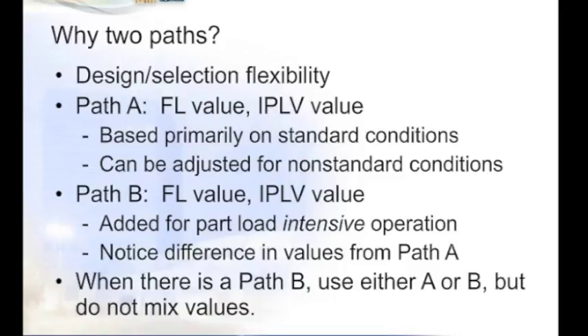When you look at the table, there's a distinct difference in the values from path A to path B, mainly in the full load and the IPLV values. The IPLVs, or the integrated part load values, are much lower than in path A, while the full load values are higher. So when you look at these values and you try to choose which path you're going in, remember that you have to choose a path. You can use path A or path B. You can't mix the values from one to the other. That's not allowed by the standard.